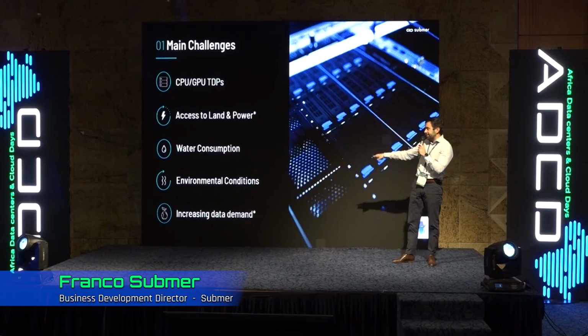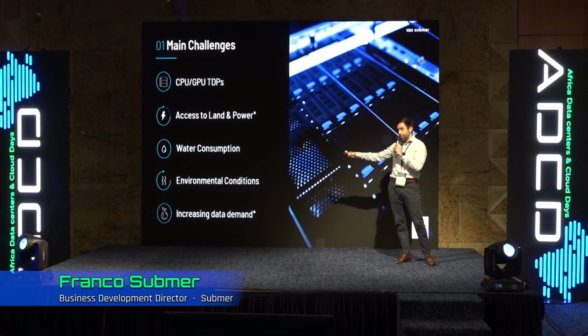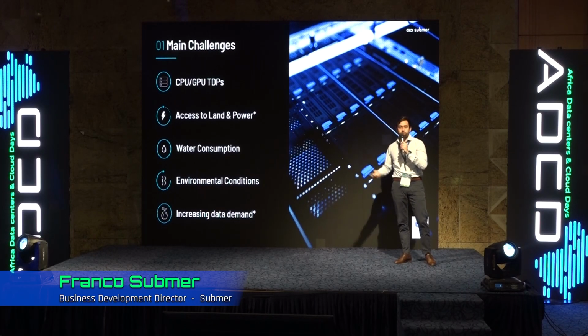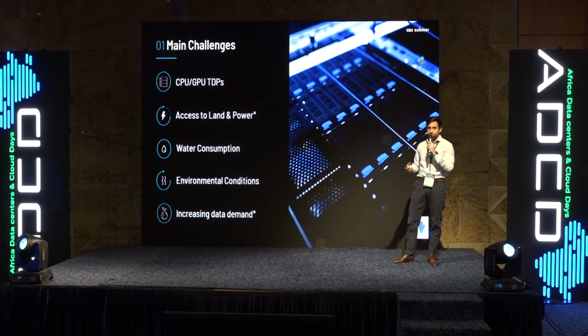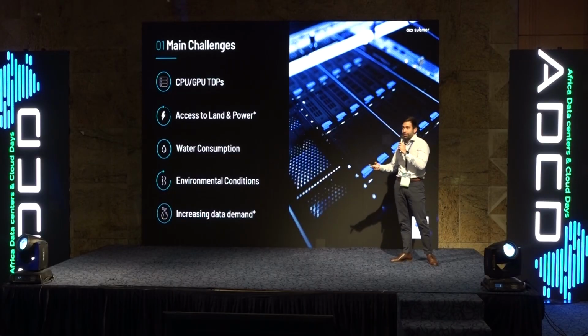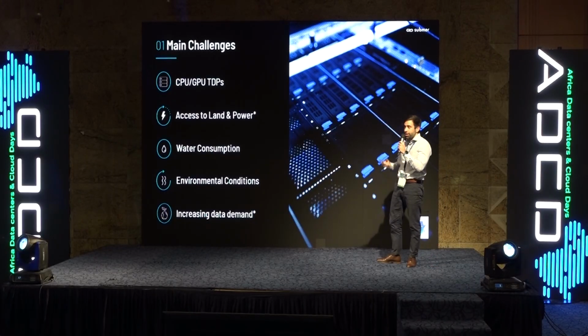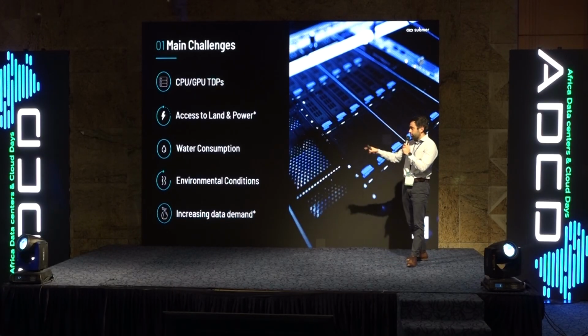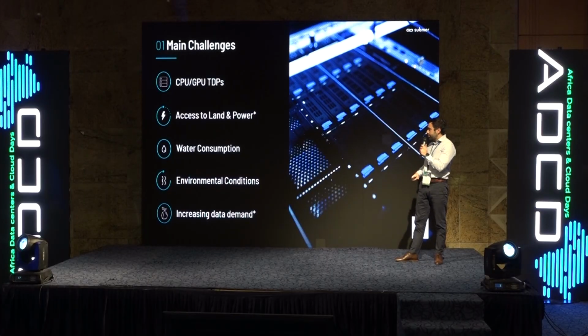The goal with this client is to reduce the PUE to 1.3, 1.4. So the challenge is the weather conditions, the temperatures you can have in Egypt—we're talking about 50, 55 degrees Celsius. And you have a data center that requires temperatures of 20 to 24 degrees Celsius, cold air. So you need to gather that type of information in your data center.